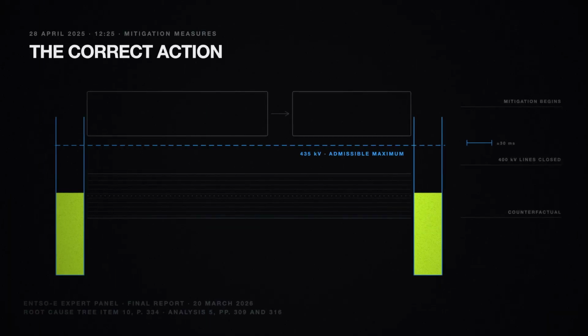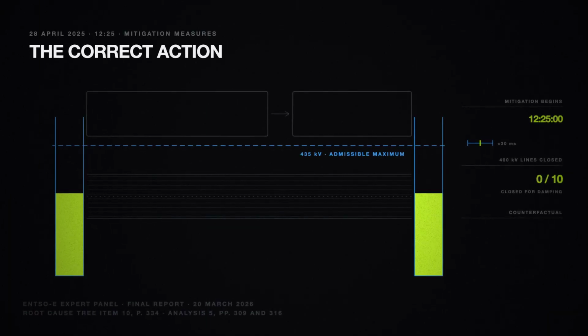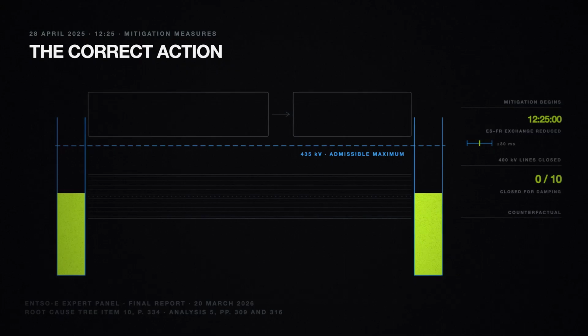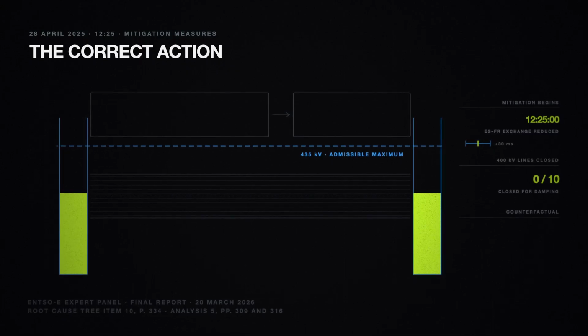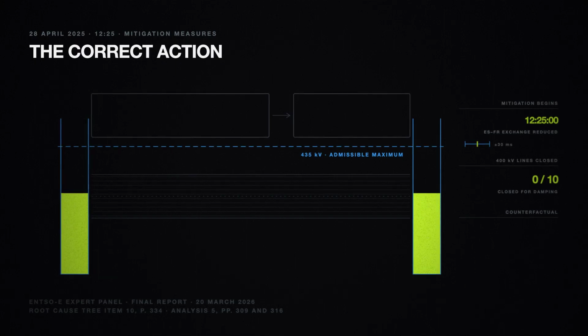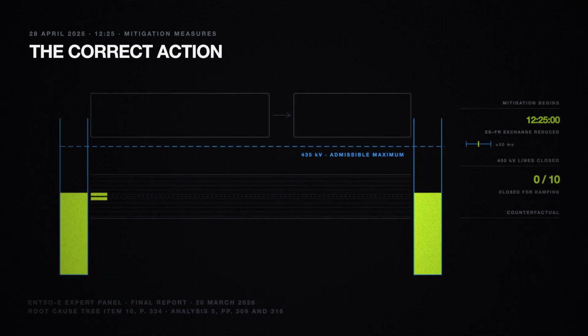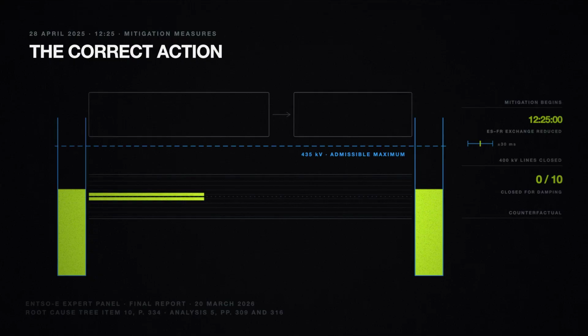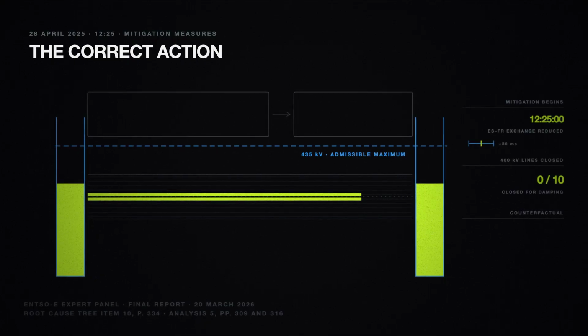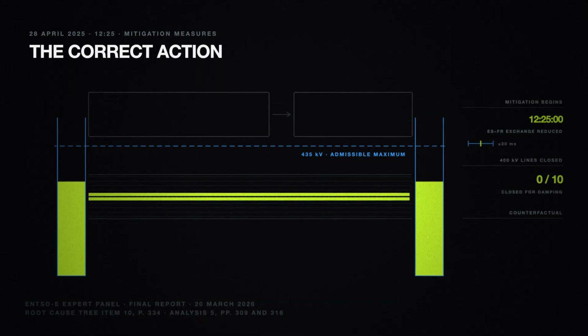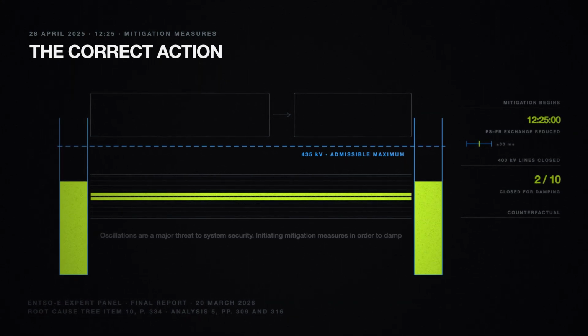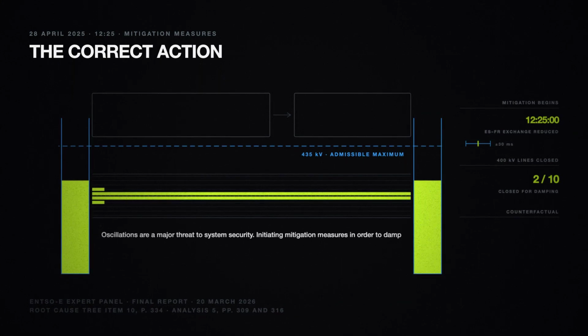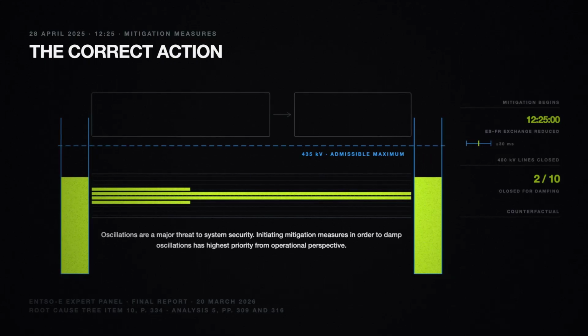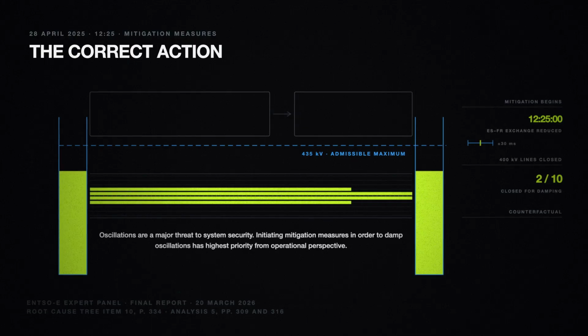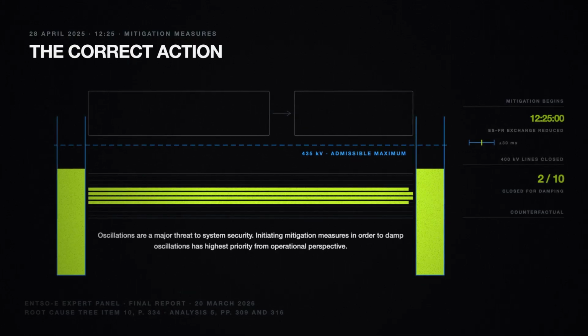25 minutes past 12. The dispatchers began closing 400 kilovolt lines and cutting the exchange on the border with France. They were damping the oscillations, which is what the procedure tells them to do. The root cause tree gives the priority in its own words. Oscillations are a major threat to system security. Initiating mitigation measures in order to damp oscillations has highest priority from operational perspective.